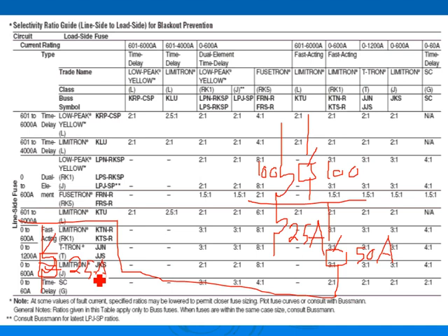You grab that 60 amp load side, you tie with number 8 wire, tie the hot to the hot and flip the switch. Do you do that? Now that will trip your main too. You know what I mean? That's what we're talking about. You're good for coordination in terms of 85% for the ground fault. But that 15% become critical for a lot of applications.